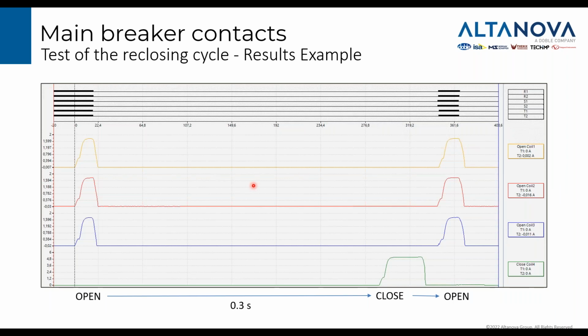This is an example of what you can get if you try to test a reclosing cycle. This is the command, and we see all the phases; in this case, we have a 2 breaks per phase circuit breaker, 6 breaks here. So we have the open command, and all the breaks change status from closed to open. After 300 milliseconds, there is a close command. Then it starts to close, and only when the main contact reaches the close position will the second open command be released, and again.